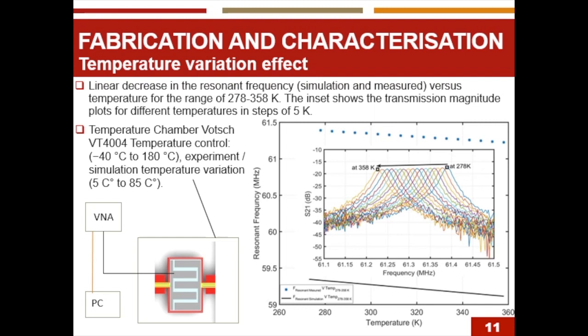Fabrication and characterization: temperature variation effect. As we said, the temperature effect on the resonator was done via ovenization effect. Mainly the resonator was placed in the oven, which is called the temperature chamber Votsch VT4004, which has a temperature control from minus 40 to 180 Celsius. In our experiment here, we applied from 5 Celsius to 85 Celsius. So we just placed the resonator inside the oven and we connected the sensor to the VNA, the vector network analyzer, which is connected to the PC to record the effect on the temperature and frequency.